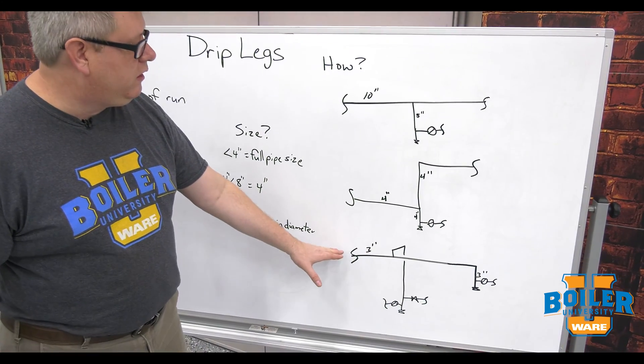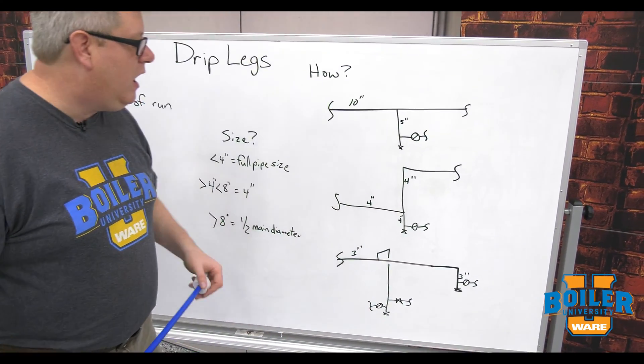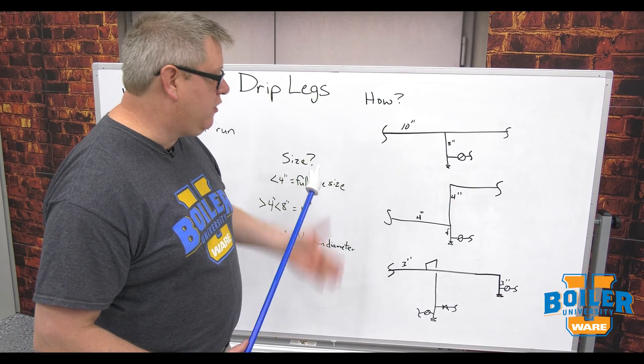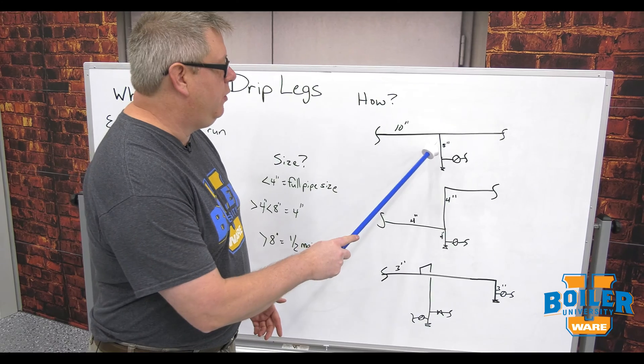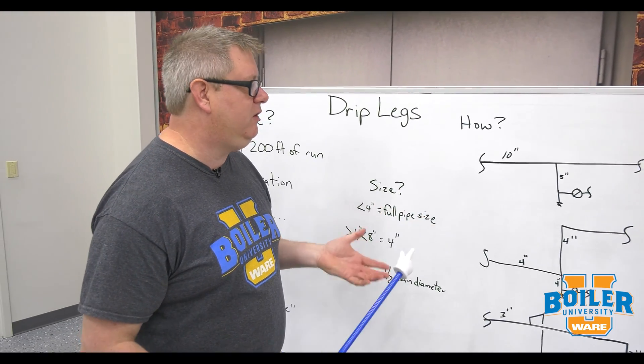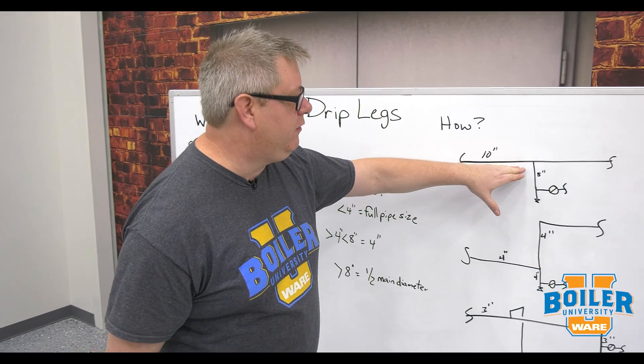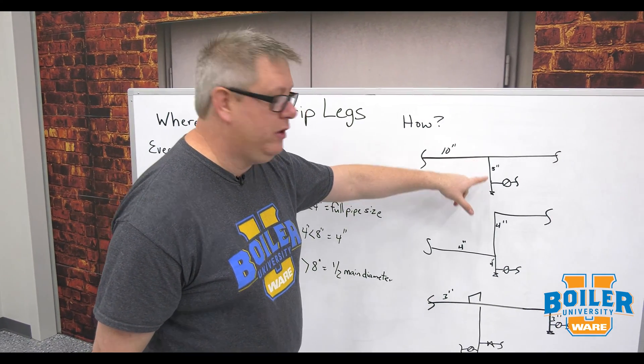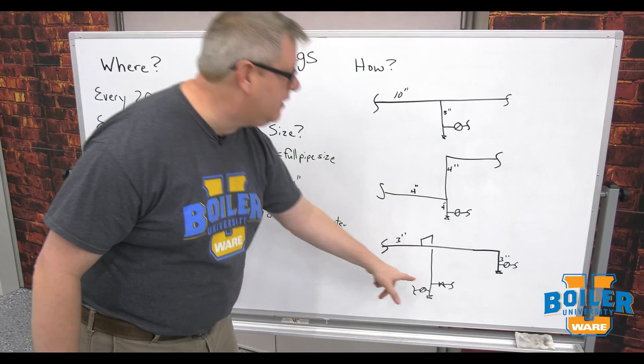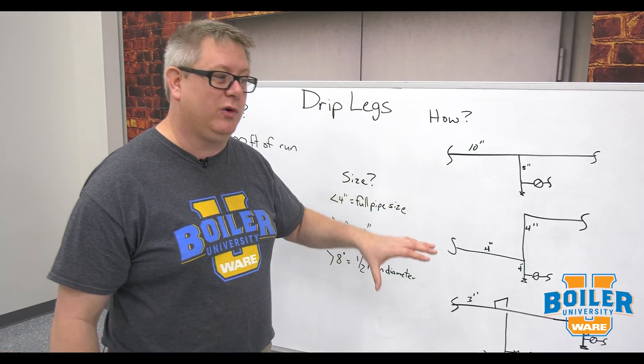We're taking a drop off to a piece of equipment. One tendency when somebody's making a drop to a piece of equipment is to pull off the bottom of the steam line because it requires the least amount of fittings and welds. But you can see from this example that's how you put a drip leg on a main. If we pull off the bottom of the pipe, we're going to get all the condensate because we're creating a drip leg, but it's going to go into our equipment.